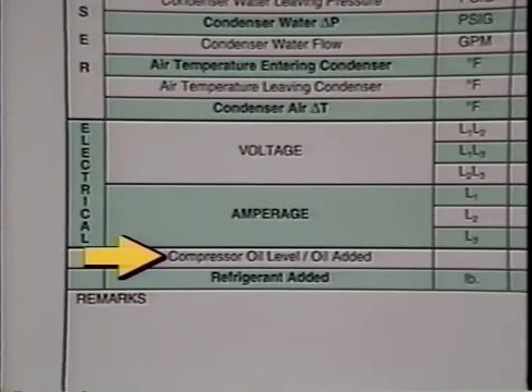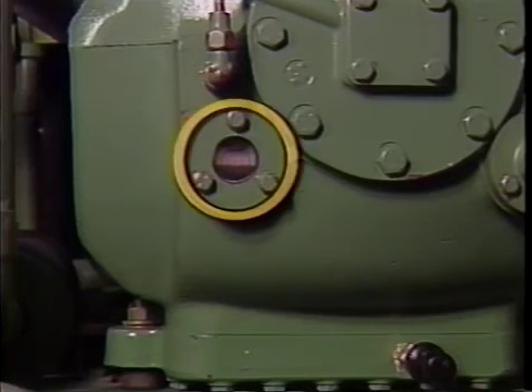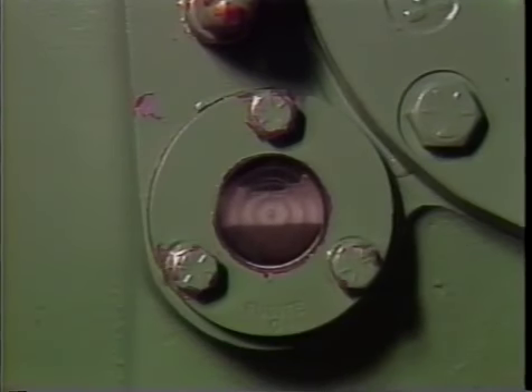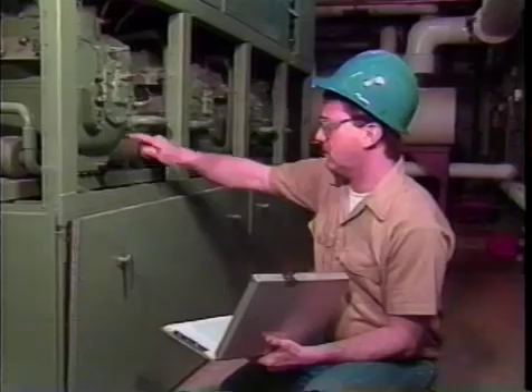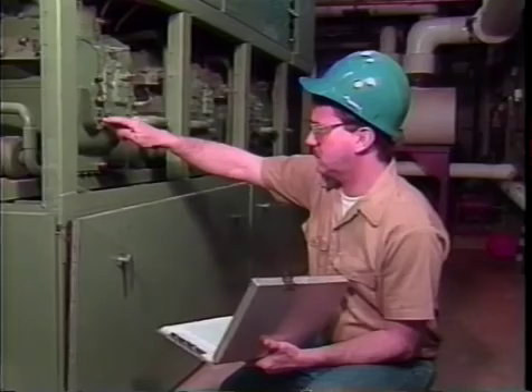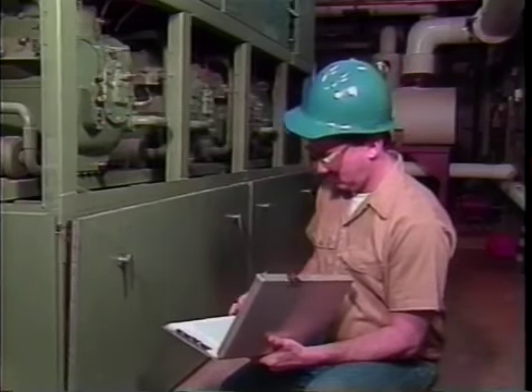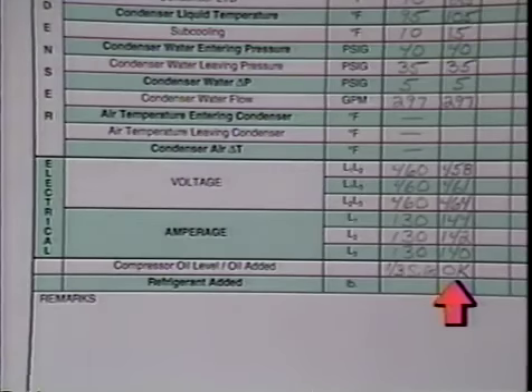Compressor oil level. On most semi-hermetic compressors, either a sight glass or bullseye is provided in the oil sump to determine the oil level. The oil level should be within the sight glass. However, under certain operating conditions, a fixed oil level may not be visible due to the foaming of the oil.